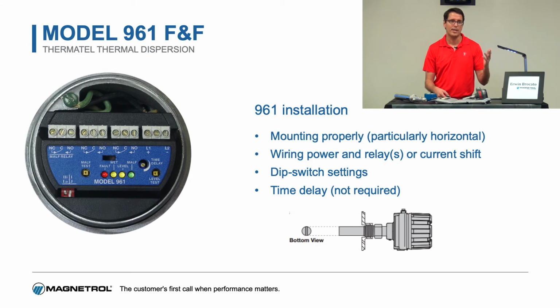Everything I was talking about over here, you've got your malfunction relay. That's the red LED; when it goes to fault, it'll show you it's gone to fault. Wet means that the sensor is wet. Level is if it detects the level. You've got a time delay. You've got a button to test the actual level as well, the level LED or the level relay, to make sure it's working before you actually install the device.